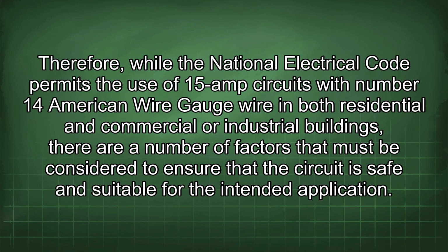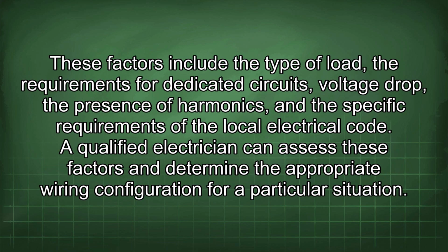Therefore, while the National Electrical Code permits the use of 15 amp circuits with number 14 American wire gauge wire in both residential and commercial or industrial buildings, there are a number of factors that must be considered to ensure that the circuit is safe and suitable for the intended application. These factors include the type of load, the requirements for dedicated circuits, voltage drop, the presence of harmonics, and the specific requirements of the local electrical code. A qualified electrician can assess these factors and determine the appropriate wiring configuration for a particular situation.